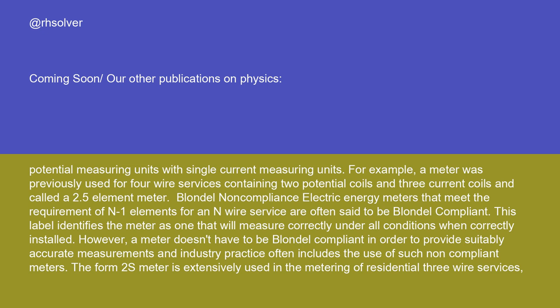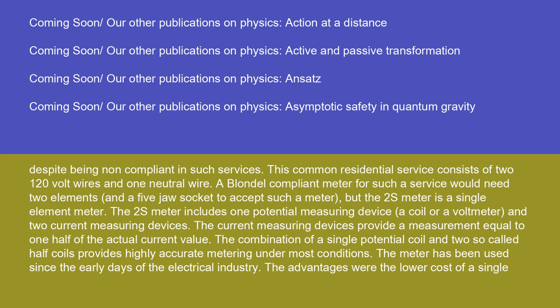This label identifies the meter as one that will measure correctly under all conditions when correctly installed. However, a meter doesn't have to be Blondel compliant in order to provide suitably accurate measurements, and industry practice often includes the use of such non-compliant meters. The Form 2S meter is extensively used in the metering of residential three-wire services, despite being non-compliant in such services.